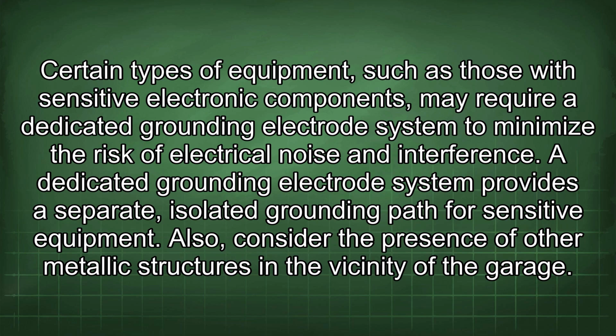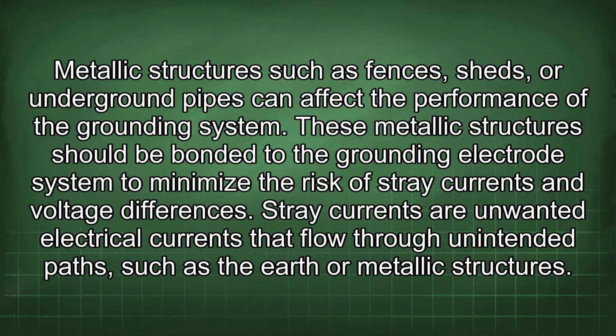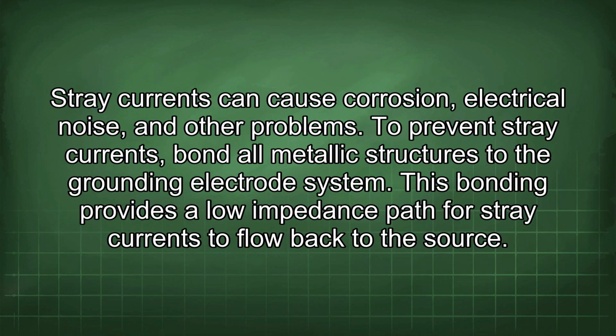Also, consider the presence of other metallic structures in the vicinity of the garage. Metallic structures such as fences, sheds, or underground pipes can affect the performance of the grounding system. These metallic structures should be bonded to the grounding electrode system to minimize the risk of stray currents and voltage differences. Stray currents are unwanted electrical currents that flow through unintended paths, such as the earth or metallic structures. Stray currents can cause corrosion, electrical noise, and other problems.